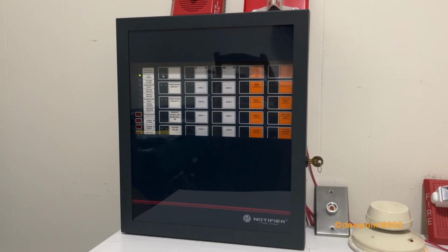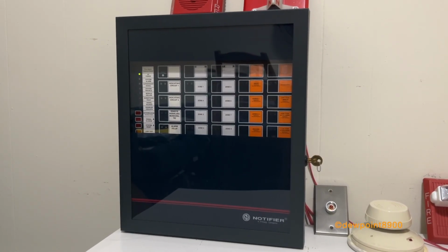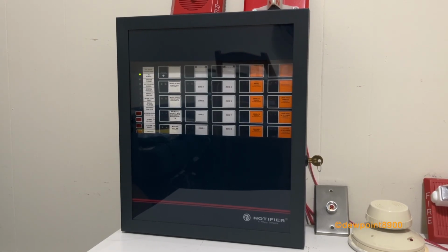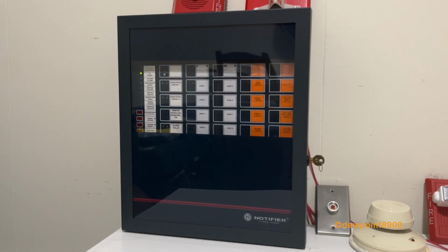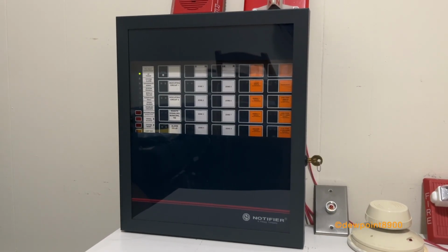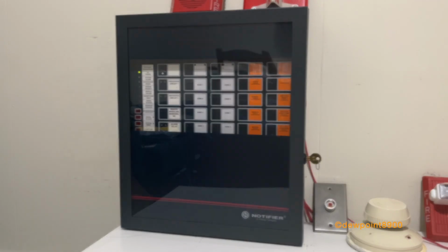Thus, in larger systems, the System 500 can act as a transponder with its own CPU and can control its own points in the event of a communications loss. While this isn't the same as the peer-to-peer networking of NotifierNet, both NotifierNet and the NIB96 networks can be mixed together to create a unique and wide array of panels across the network.